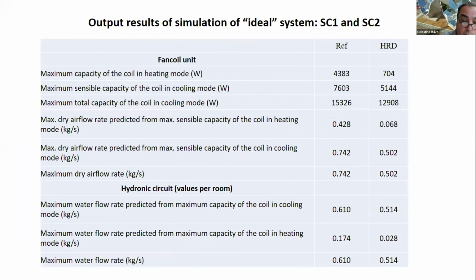In this table, we present output performance results of the ideal system simulated in the first step for the reference configuration without heat recovery and for the configuration with the recovery device. With the thermal capacity values of the cooling coil and of the heating coil, the airflow rates of 0.742 kilograms per second and 0.502 kilograms per second were determined for reference configuration and when using the heat recovery device, which corresponds to an important reduction of 32% in the airflow rate.